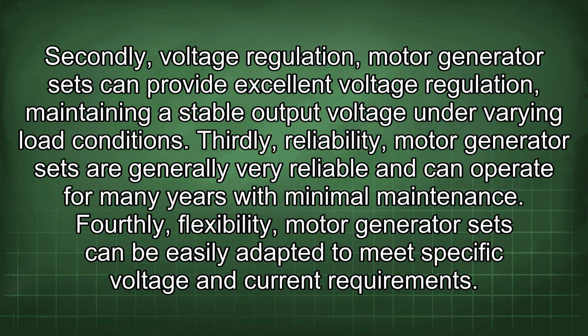Secondly, voltage regulation. Motor generator sets can provide excellent voltage regulation, maintaining a stable output voltage under varying load conditions. Thirdly, reliability. Motor generator sets are generally very reliable and can operate for many years with minimal maintenance. Fourthly, flexibility. Motor generator sets can be easily adapted to meet specific voltage and current requirements.